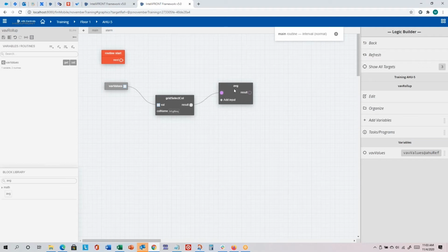This is a case I mentioned where the averaging block should only have one input. And I mentioned earlier that if for some reason you added an input, you can't back your way out of it the way you can for the third one. And it won't work right if you have an unconnected slot. So if you ever added a second one and didn't need it, then you can right click and delete any links going into the averaging block, delete the averaging block by selecting it. You'll see a yellow border, press the delete key on your keyboard, and then just drag a new averaging block in.